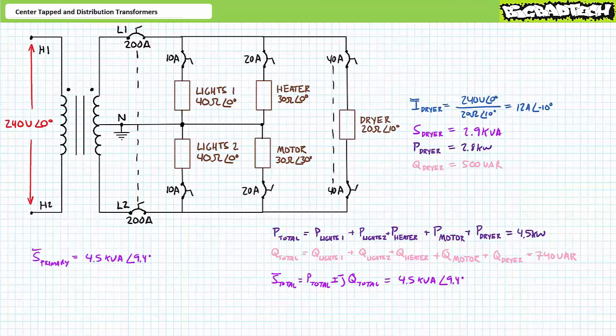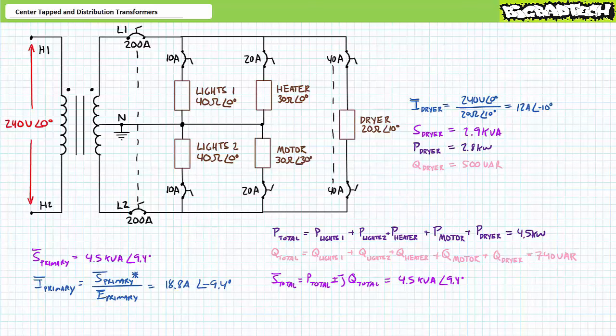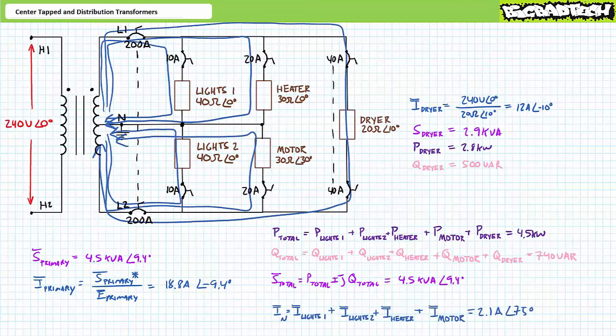If we were to assume this transformer is 100% efficient, the primary must also provide 4.5 kilovolt amperes of apparent power. An algebraic manipulation of the AC power formula solving for current demonstrates the 240 volt primary draws 18.8 amps at an angle of negative 9.4 degrees. Given the dryer does not necessitate the neutral line, current in the neutral line remains 2.1 amps at an angle of 75 degrees — i.e. the degree of imbalance between that drawn from phase L1 and phase L2.